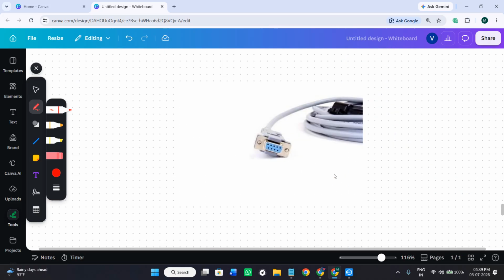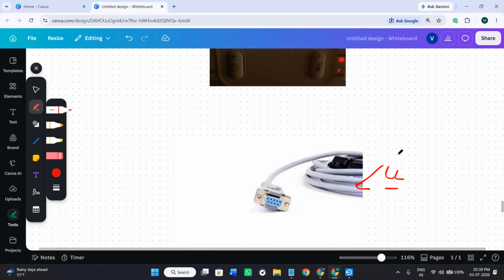Then you need to inspect the communication cable running between the indoor and the outdoor units. If it has become loose, damaged or disconnected after the installation or maintenance, the two units won't be able to communicate properly. So make sure that this particular communication cable is linked properly.